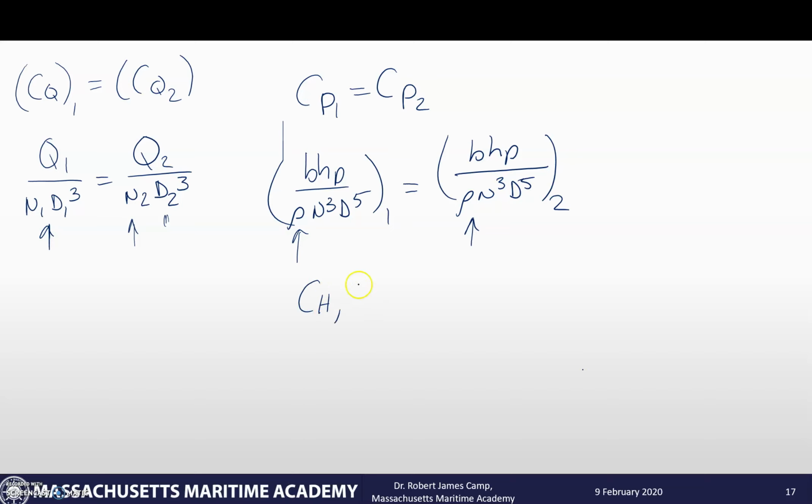Once you figure out that information, you can flow that impeller speed back into your coefficient of head and coefficient of capacity equations to figure out how the head and the flow rate have been impacted by those changes.